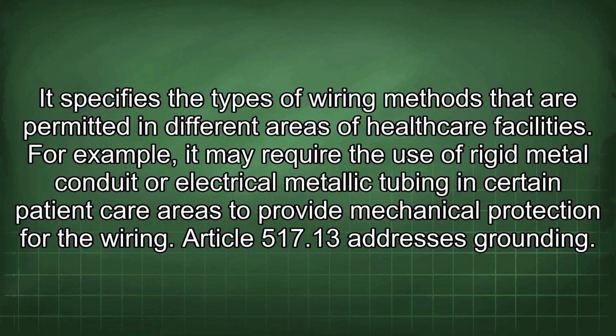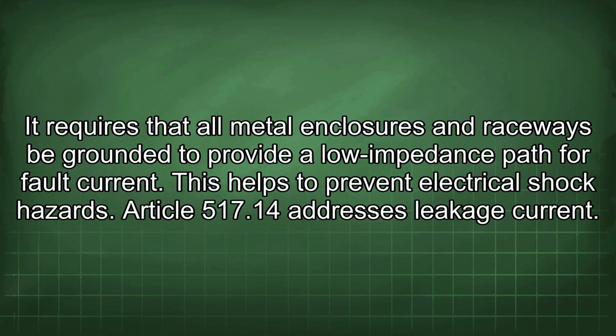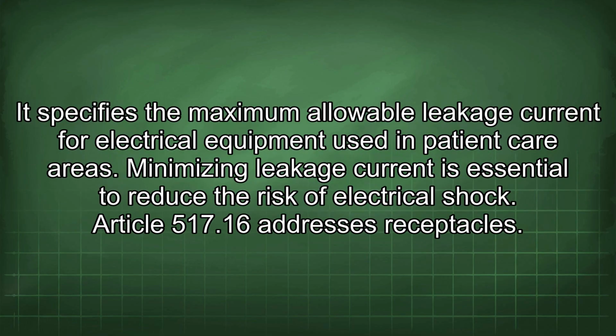Article 517.13 addresses grounding. It requires that all metal enclosures and raceways be grounded to provide a low impedance path for fault current. This helps to prevent electrical shock hazards. Article 517.14 addresses leakage current. It specifies the maximum allowable leakage current for electrical equipment used in patient care areas. Minimizing leakage current is essential to reduce the risk of electrical shock.